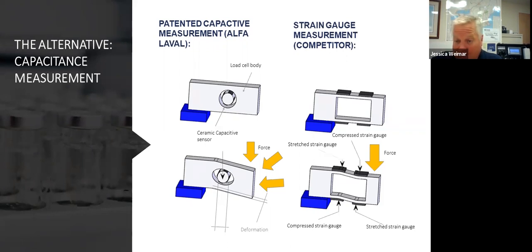Okay, and you can see if I load the heck out of this on the bottom right-hand side picture, you can envision that that sensing mechanism is subject to that load as well. If you look over to the left-hand side, though, here's what we're going to talk about today, and this is called the capacitance measurement system. Same thing's happening. The beam is deflecting, just like we talked about with the strain gauge unit. But what's different, and this is really important, and again, this is kind of proprietary technology, is there's an element that's suspended inside the cell, and there are ceramic sensing units that are adhered to that element, and what they're going to measure is a proximity change from the adjacent surface of the cell as it deflects.